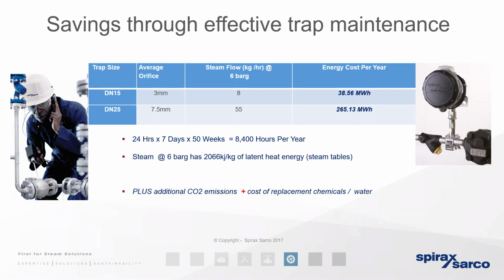So it's highly encouraged that steam using sites undertake a periodic audit. Now that could be a manual audit that is undertaken typically once a year. The steam trap will be checked for operation, open or closed. It will be checked to see if it's the right type of trap or if it's been sized or installed correctly. If it hasn't, well, the appropriate modifications can be made and we can enjoy a significant payback. Or in more sophisticated processes, the trap operation can be monitored automatically in real time, where a reading can be relayed automatically to a BMS or even to a computer or even a mobile phone to advise when a trap's being left in the open position or closed position, so the maintenance team or production team can take the appropriate steps.